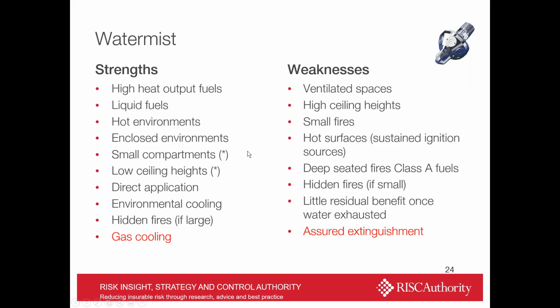Now, I think hopefully you've started to get a good handle on what the strengths are of Watermist. Very good on high heat output fuels, and particularly liquid fuels, hot environments, enclosed environments. This optimizes steam production and containment of that steam for displacement of oxygen as well. Best for small compartments with low ceiling heights. Now, the reason more for this is because that can also maintain the momentum of the droplets themselves. Around a fire, there are a lot of repelling forces to drive droplets away, and Watermist systems overcome this by generally injecting them in a fairly fast and furious fashion so that they can overcome these repulsive forces.